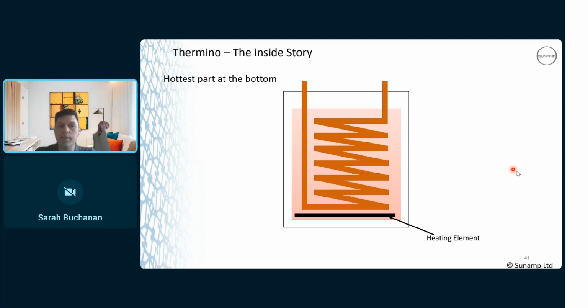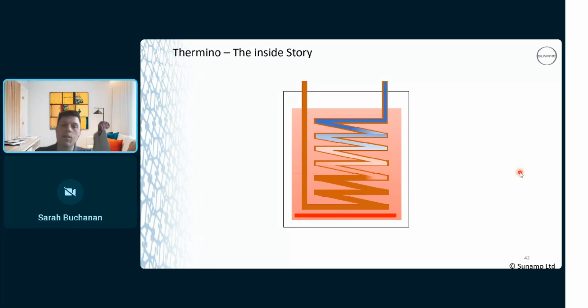Talking about the operation, we've got a heating element at the bottom, so we're charging from the bottom up. Cold water comes in and we start discharging from the top down. The way I like to think of it, the water is preheating as it's going through the battery, and it's depleting the storage. So it's important to make sure that if you're using a timer, the timing cycles are set correctly for the size of the unit.